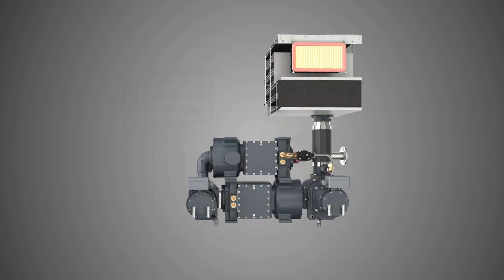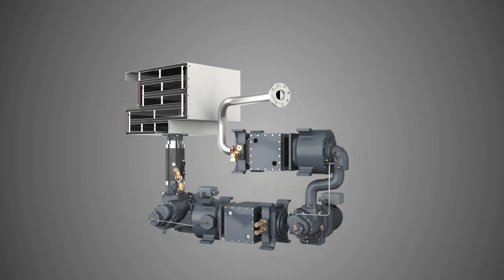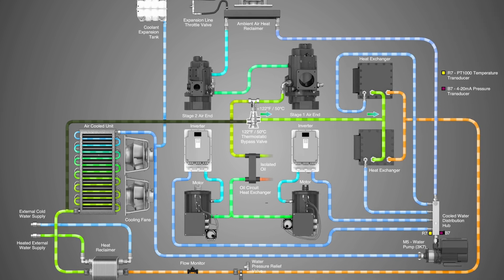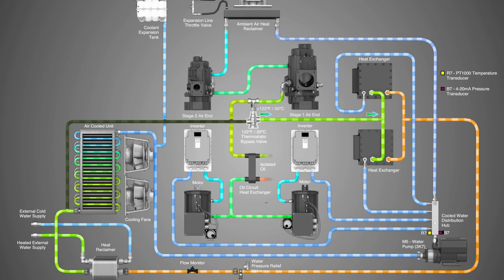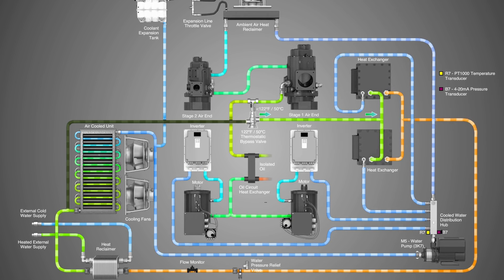Here's how the integrated heat recovery system works. During the air compression process, waste heat is captured and transferred through the compressor closed-circuit cooling water loop to the plate heat exchanger, also integral to the air compressor. This heat is then transferred through the heat exchanger to water in a separate closed-loop water circuit connected to a calorifier, where it is used to heat water to 65 degrees Celsius for domestic use in the plant, such as showers, wash basins, etc.